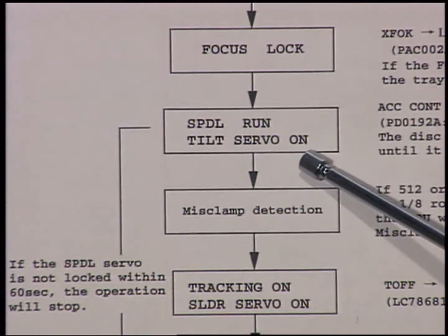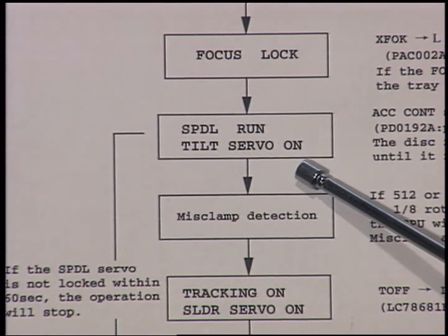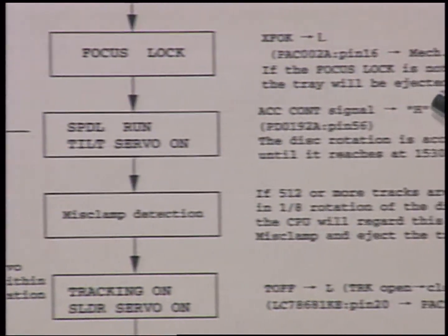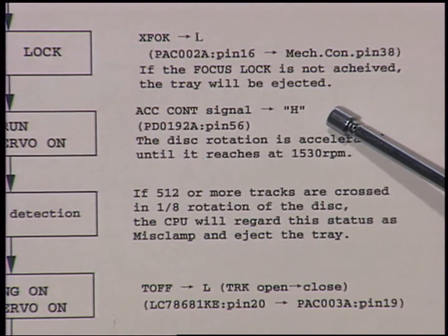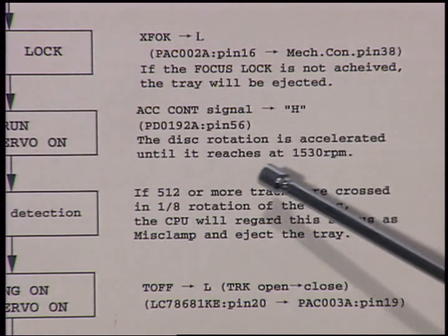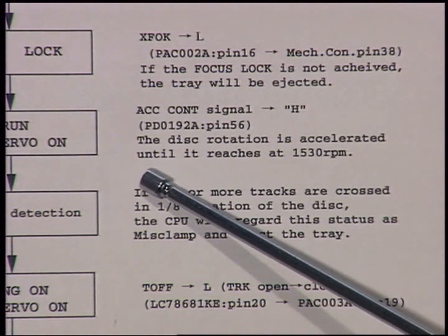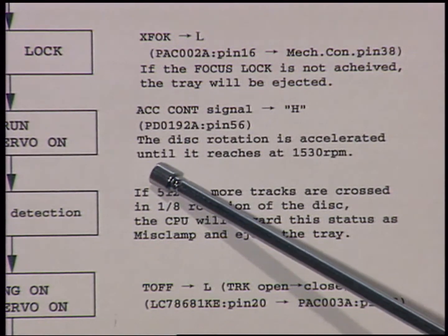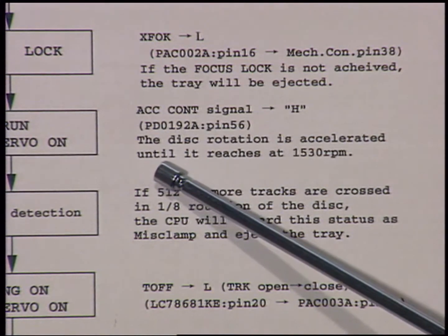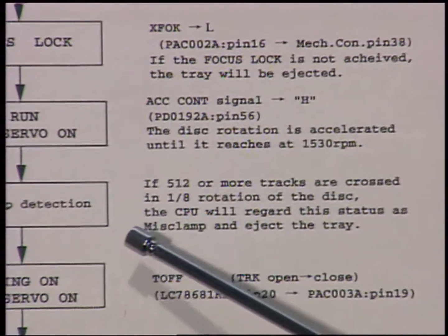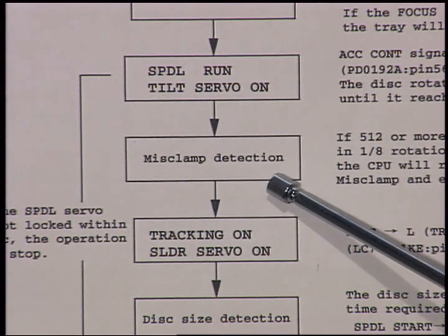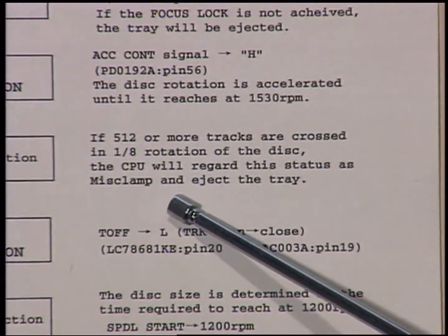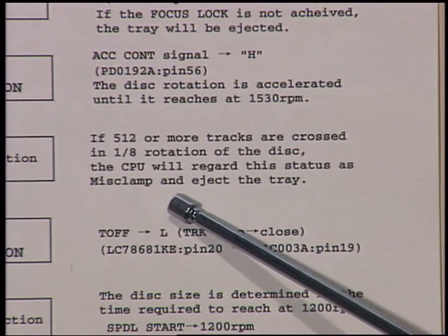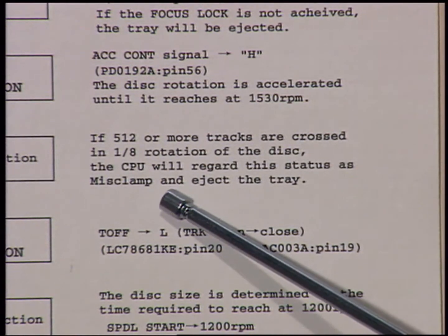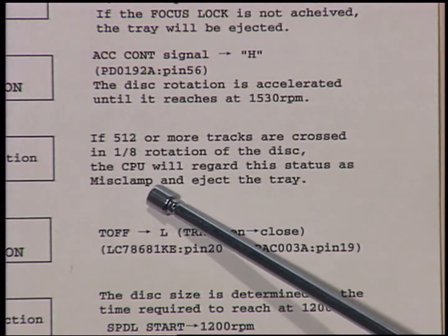After that, spindle run and tilt servo on are activated at the same time. The ACC CONT signal turns to high, and the disk rotation is accelerated until it reaches 1530 RPM. After that, misclamp detection is done. If 512 or more tracks are crossed in 1/8 rotation of the disk, the CPU will regard this status as misclamp and eject the tray.